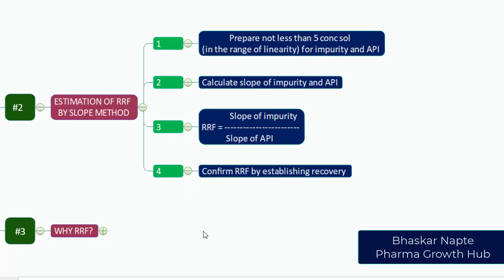You need to confirm the RRF by establishing recovery studies. If you have a recovery limit of 90 to 110 percent, apply the RRF factor for the accuracy study and confirm whether your recovery studies are within the 90 to 110 percent range.